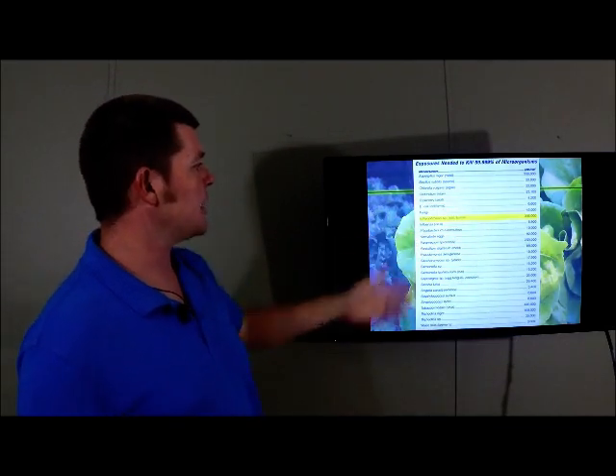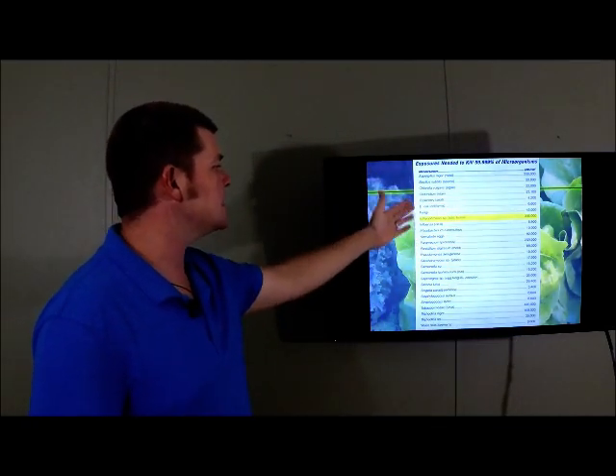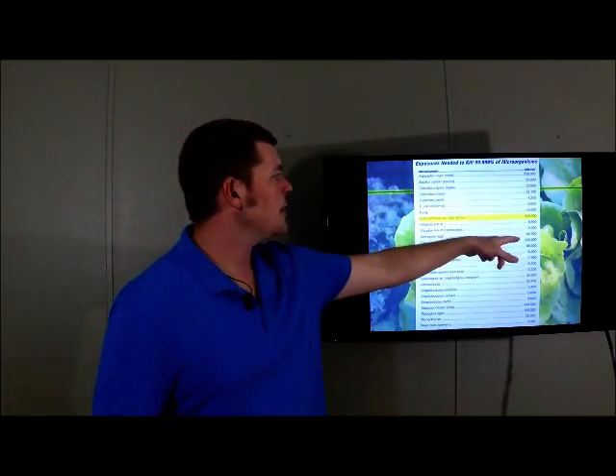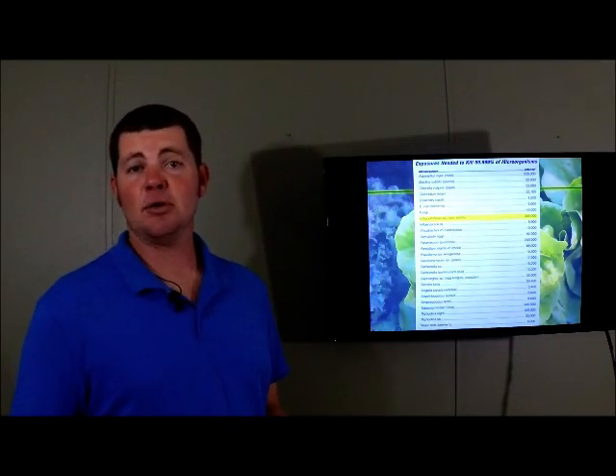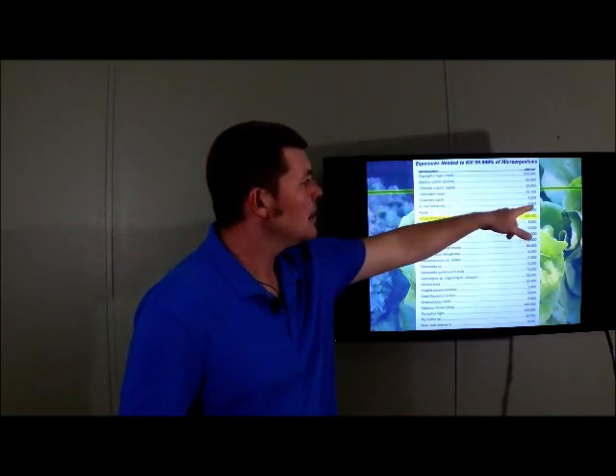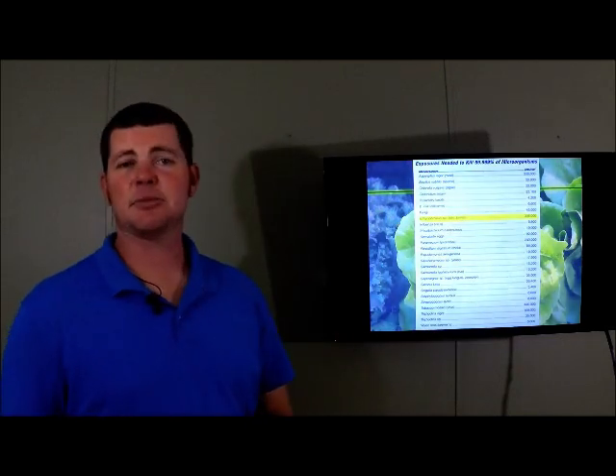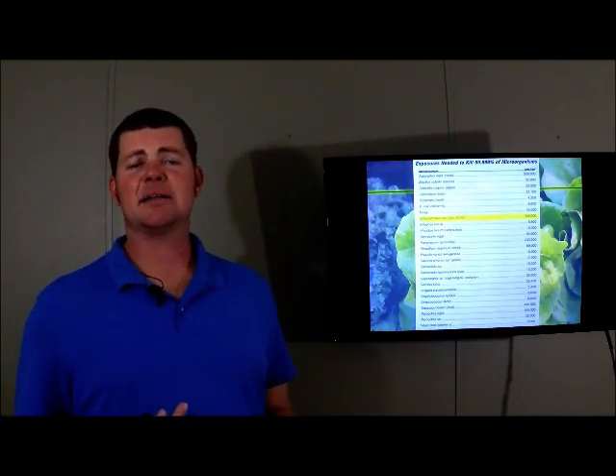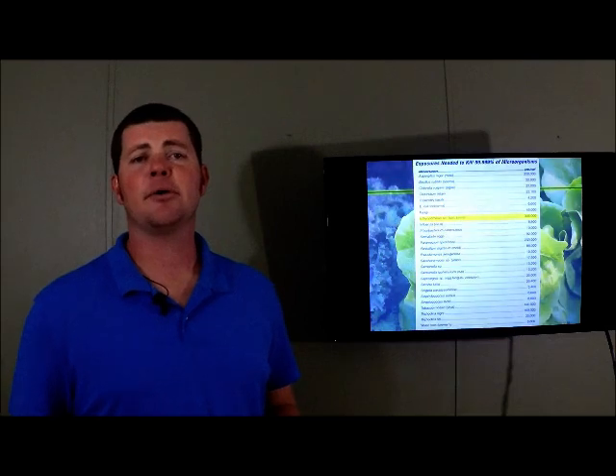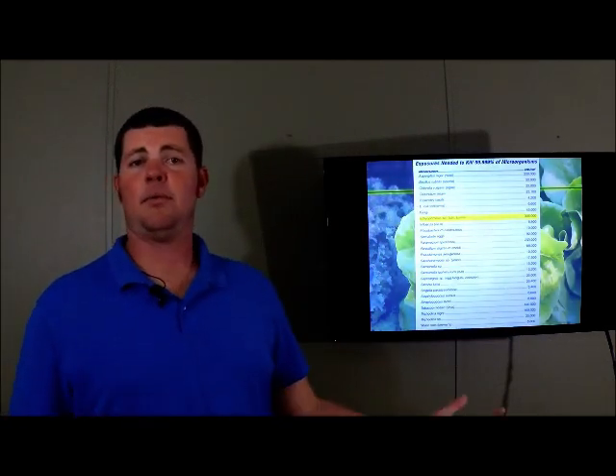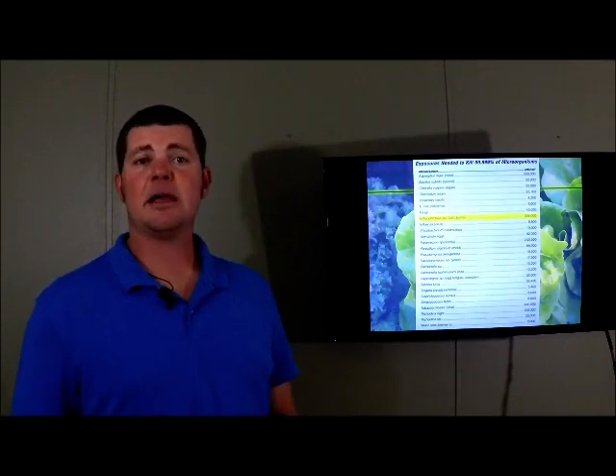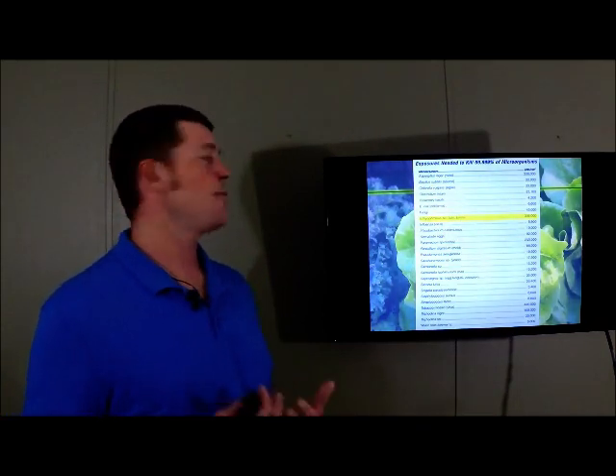Quick chart right here. It's kind of hard to see through the camera, but you can look at it on the PowerPoint, and it gives you a nice little list of organisms, pathogens, and what the exposure rate of UV is to actually kill or sterilize that pathogen, okay? So E. coli, we look over here, 6,600 microwatts per centimeter squared. And we're talking about sizing just off a general number, 30,000. So we would eradicate E. coli, which is a wonderful thing. Any E. coli in that water column, we would go ahead and eradicate it.